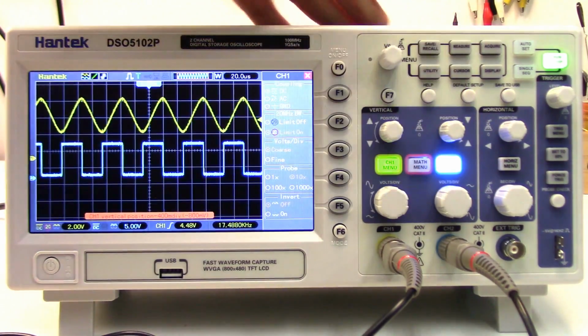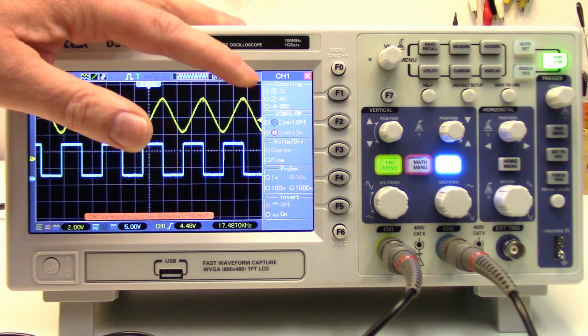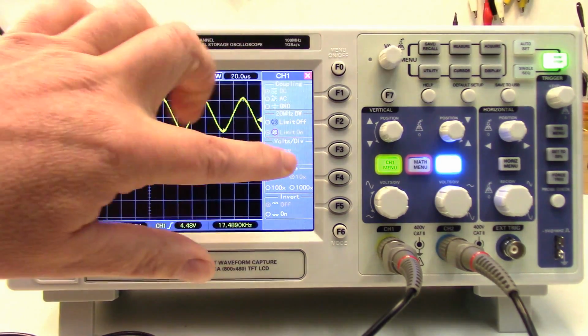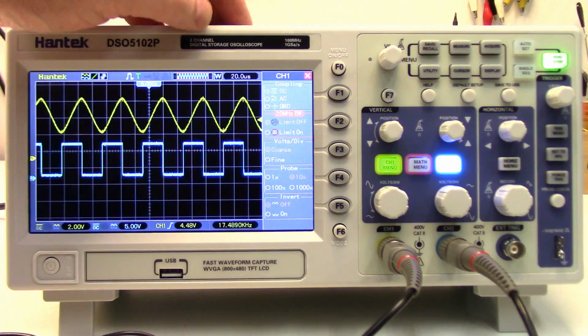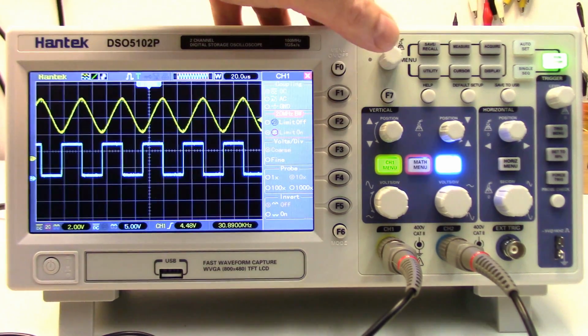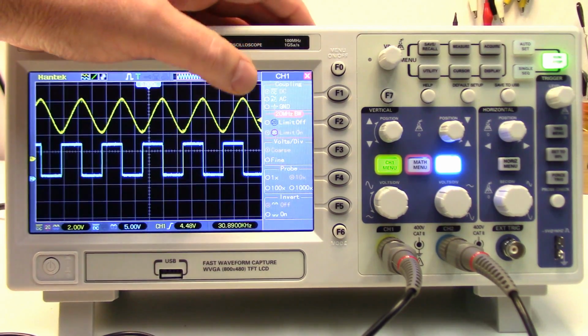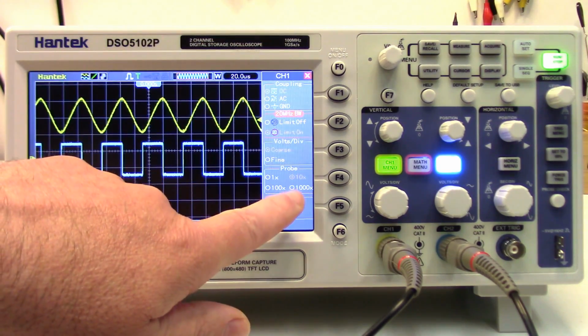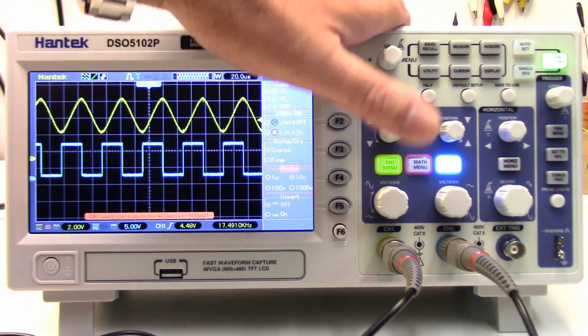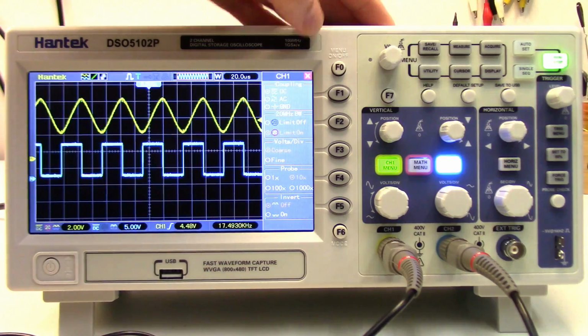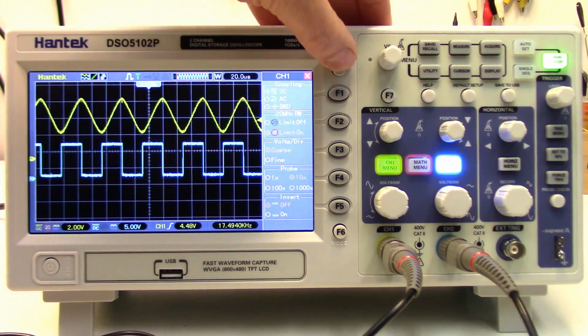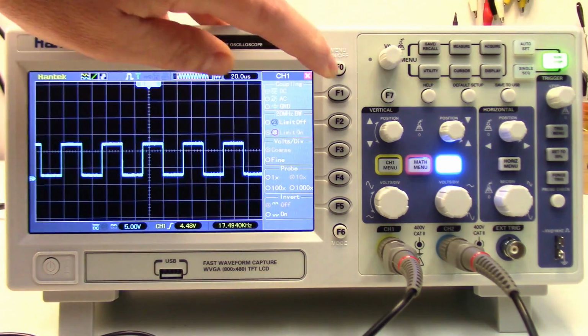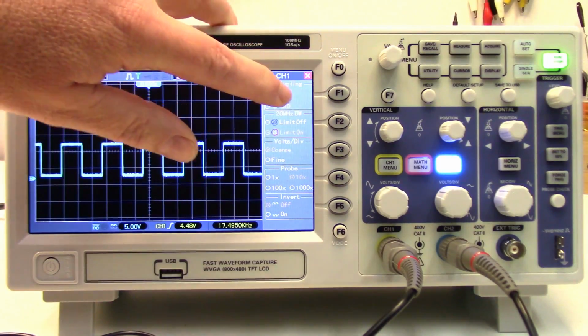Just to show you what the channel menu looks like. It's got the coupling type. You can limit the frequency to 20 megahertz. That just eliminates a lot of noise when you have that selected. And you can have coarse or fine voltage adjustment. This is where you would change your probe attenuation if you had it at 1 times, but we've got it at 10 times. To get out of the menus, you just push the F0. And I don't know if you noticed that, but all the function buttons line up really nicely to every one of the selections in the window here.